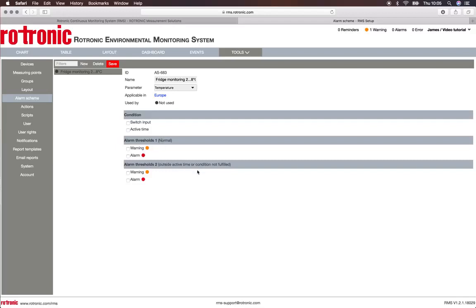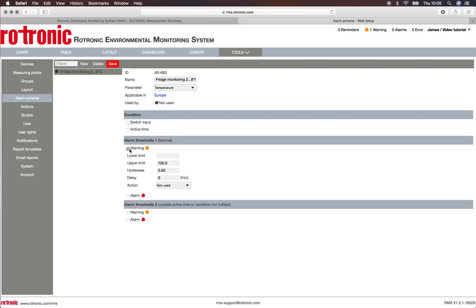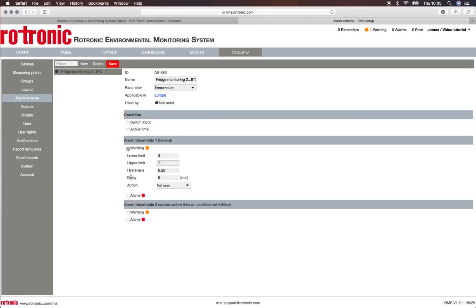I'm really interested here during the normal working period, so I can put a warning. The warning lower limit is, let's say, 3. The higher limit is 7, hysteresis of 0.5, delay of 0.